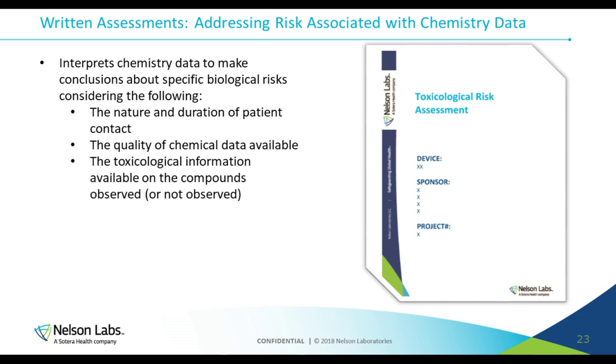So it evaluates that. Now, the thing about toxicological risk assessments that I want to mention, and the reason why I bring it up right here, is because the conclusions that the toxicologist needs to make depend on the chemistry data, and it depends on the quality and the type of chemistry data available. So if you have chemistry testing followed by toxicological risk assessment as part of your plan, you really need to start your conversation with the toxicologist first before you order the chemistry testing or before you start too far down that path, because it could be that the toxicologist knows that they have very special requirements on what that testing needs to look like in order for them to feel confident in making their claim.